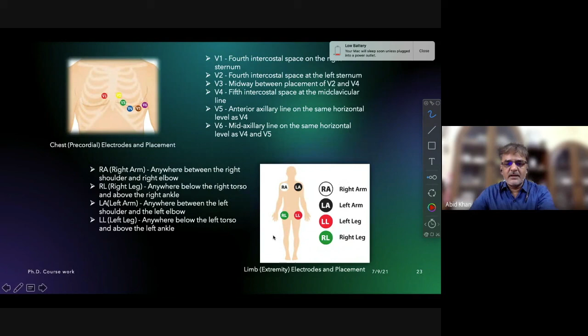So these are basic methods for measuring biosignals. In biosignals, it is very important to keep earthing to reduce noise, because every signal may be affected by noise, and this noise has to be reduced by putting an earth somewhere around a bony part. That's why in ECG or EEG or EMG, we all use an earth wire to earth the unwanted electrical activities that mix with the signal.